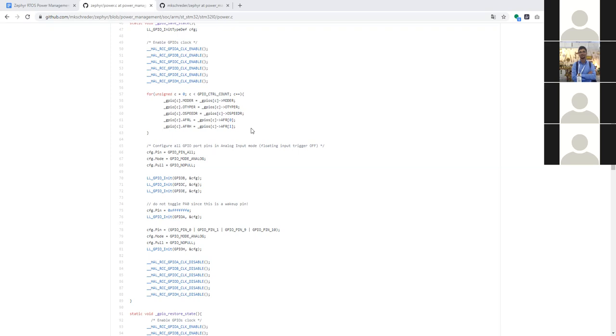Oh, so in case of IEC 61508 or for medical devices, yeah. So, because you see, if we use an RTOS, then we need to go through a specific process of certification. If we use a certified FreeRTOS, so SafeRTOS, we need to pay for the licenses, but of course it's certified already. But from what I understand, if Zephyr comes out with a certification already, as a pre-certified component, then it should be a good starting point for us to leverage the certification and just develop and certify part of the component we are developing. So not the whole product, but just a small part of the firmware.